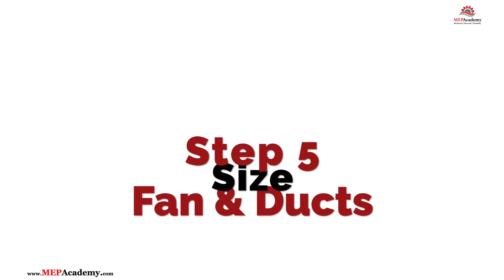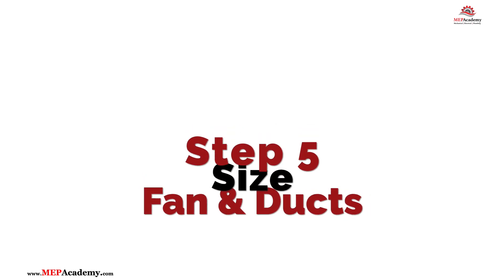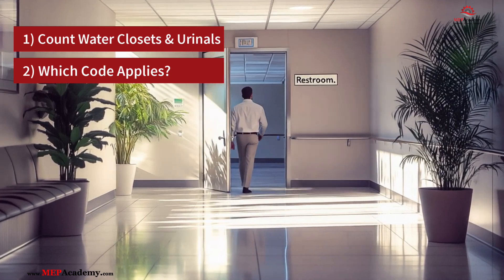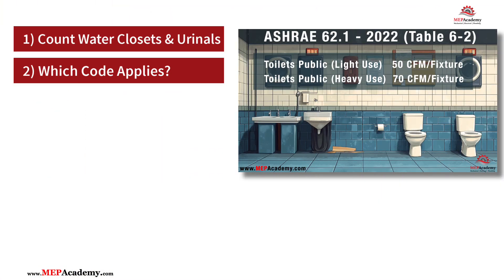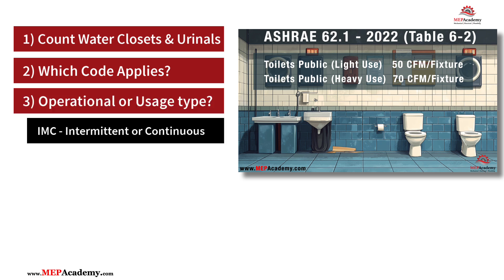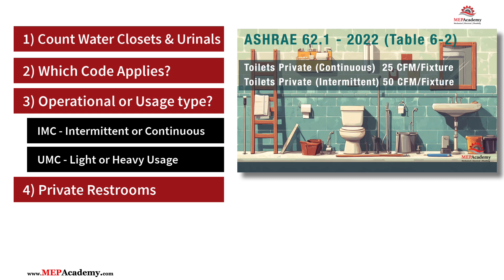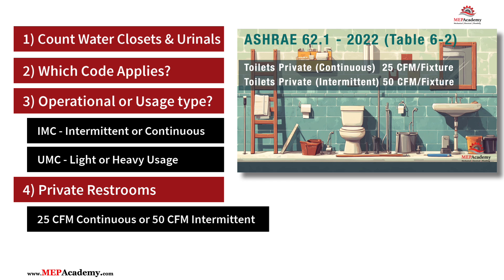Step 5: Select exhaust fans or design ductwork to meet or exceed the total CFM requirements. To summarize: (1) Size exhaust fans based on fixture count and usage intensity. (2) UMC 2024, IMC 2024, and ASHRAE 62.1 work together to guide airflow requirements. (3) Always confirm whether fans operate intermittently or continuously, and if using UMC, whether use is light or heavy to apply the correct rates. (4) For private-use restrooms, the required exhaust is 25 CFM for continuous or 50 CFM for intermittent system operation.